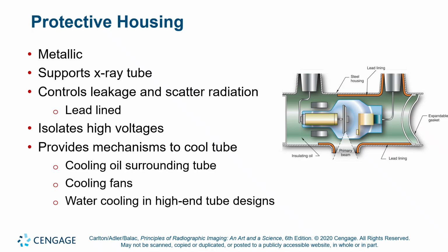If the insulating oil is leaking, one of the jobs of the insulating oil is to effectively cool down the tube. So if the insulating oil is leaking, how is it maintaining its volume? If it's not maintaining its volume, that means there's an air bubble inside the tube housing. That means the tube is not cooling down effectively. And so the other fundamental flaw, other than exposing your patients and your technologists to a known carcinogen, is you're running an X-ray tube when its heat dispersion mechanism is not operating as efficiently as it ought to. Okay.